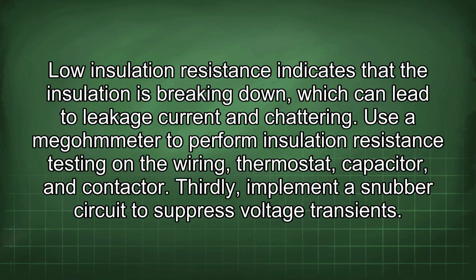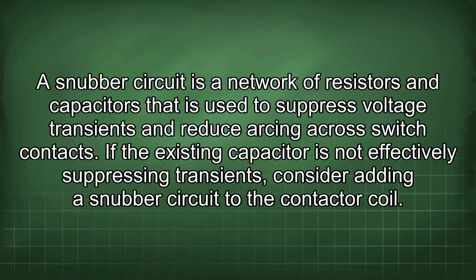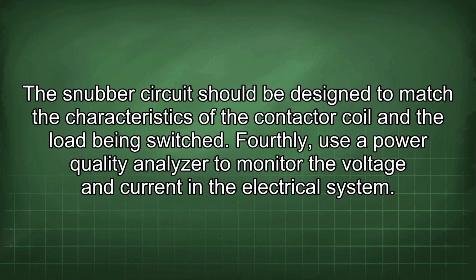Thirdly, implement a snubber circuit to suppress voltage transients. A snubber circuit is a network of resistors and capacitors that is used to suppress voltage transients and reduce arcing across switch contacts. If the existing capacitor is not effectively suppressing transients, consider adding a snubber circuit to the contactor coil. The snubber circuit should be designed to match the characteristics of the contactor coil and the load being switched.